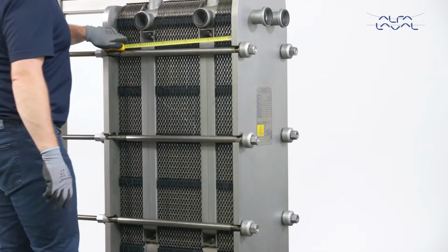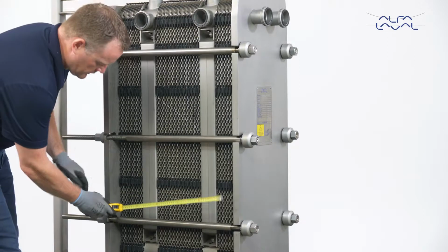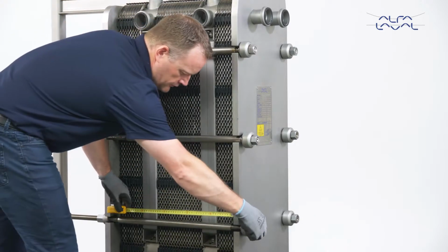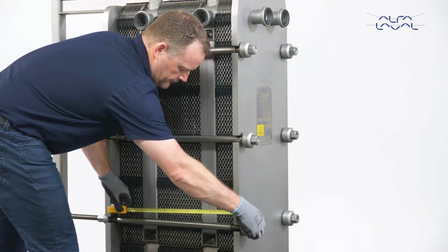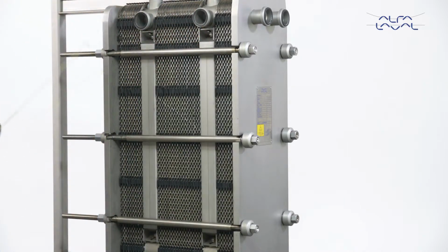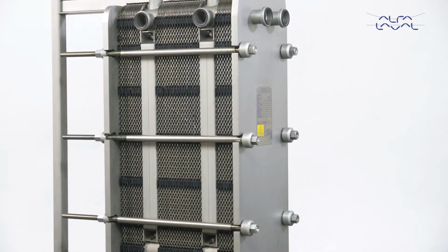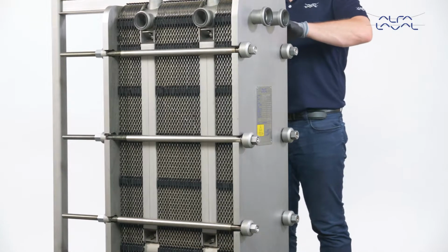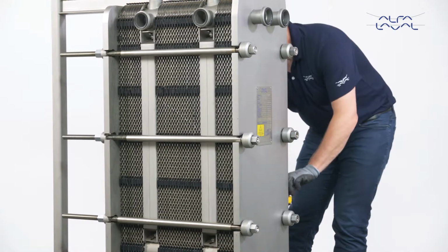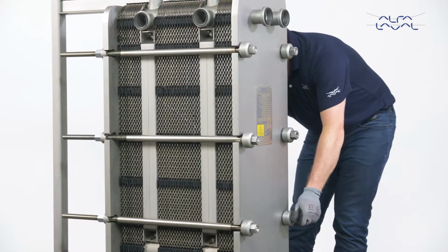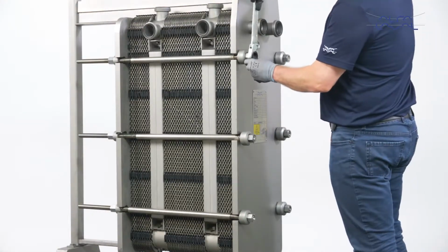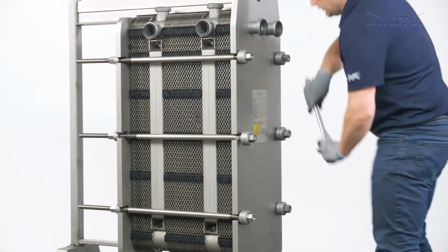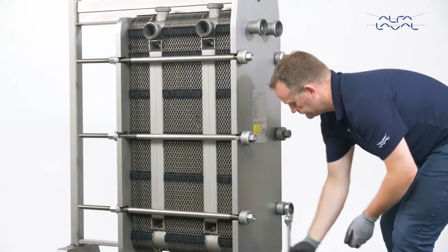Make sure the frame plate and pressure plate are parallel to each other before tightening further by checking the A measurement, which is the distance between the frame plate and the pressure plate. Now continue to tighten the 4 tightening bolts in sequential order, following the diagonal pattern, and remember to check the A measurement regularly.